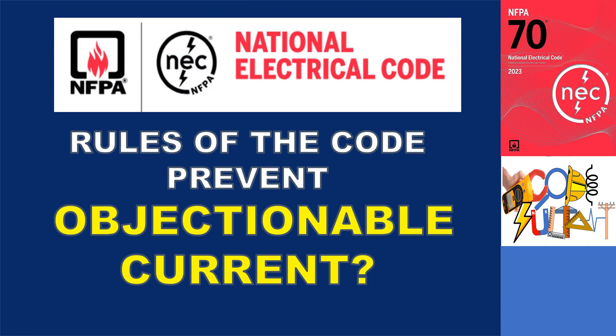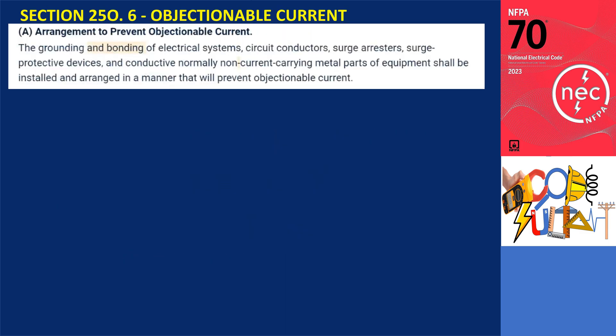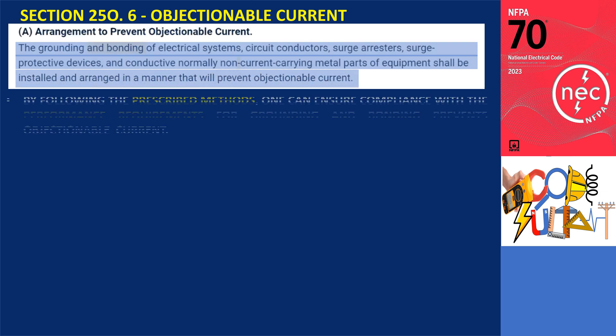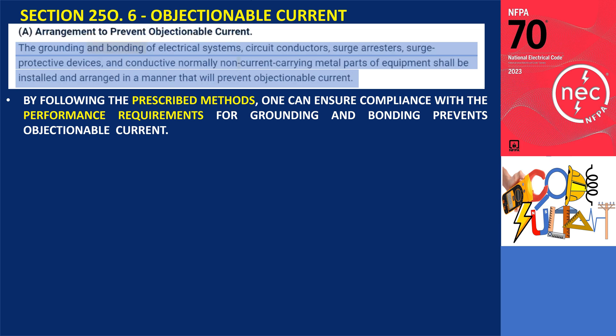The National Electrical Code has rules and guidelines in place to prevent objectionable currents and ensure safe electrical installations. Section 250.6A of the NEC provides specific guidance on how grounding and bonding should be arranged to prevent objectionable currents. This section states that the grounding and bonding of electrical systems, circuit conductors, surge arrestors, surge protective devices, and non-current carrying metal parts of equipment should be installed and arranged in a manner that prevents objectionable currents. Following the prescriptive method for grounding and bonding as outlined in Article 250 of the NEC can help prevent objectionable currents from occurring.